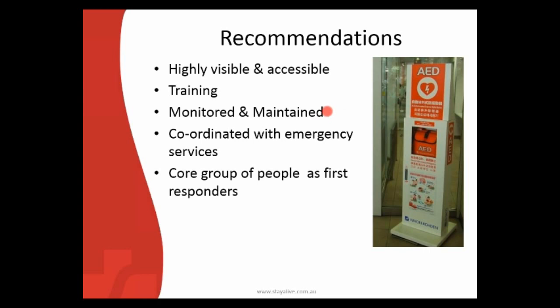They need to be monitored and maintained. Absolutely. At least monthly, somebody needs to check the defibrillator. Make sure that the electrodes that go on the chest are in date. They have an electroconductive gel that's sticky, that sticks it to the chest, and that will eventually dry out and crack depending on the manufacturer. Lifetimes vary, but you need to make sure that they're in date so that you never have a situation where you have dried, expired pads that you can't really use on somebody because they're all dried up. That's not going to save a life.